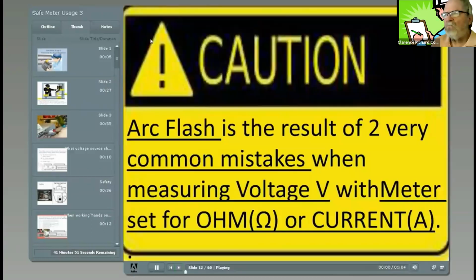Then you are performing a series of measurements on an electrical service panel. You have just finished measuring a small current draw for some ancillary piece of equipment, and you want to measure the circuit voltage so you can calculate power consumption. Your assistant is holding the meter and switches it from the current function to the voltage function, but forgets to switch the test leads from the current terminal to the voltage terminal. Pow! Another common meter misuse can occur when making a resistance measurement. This happens when you make contact with a circuit you thought was dead, when it was actually live.